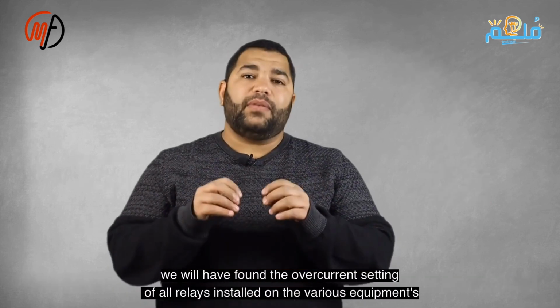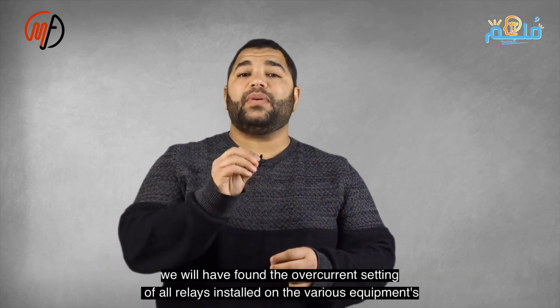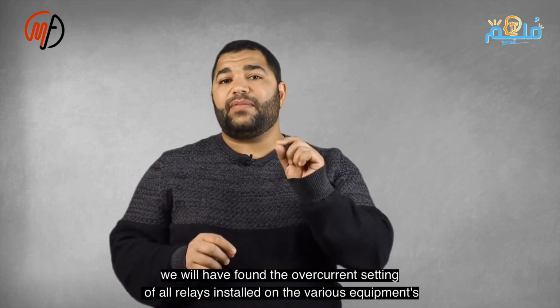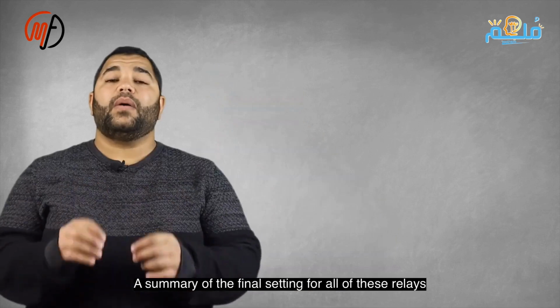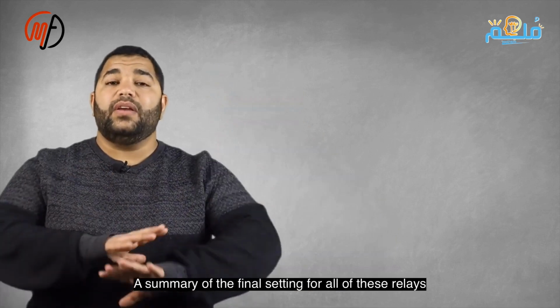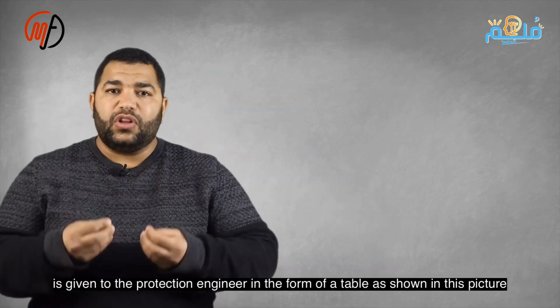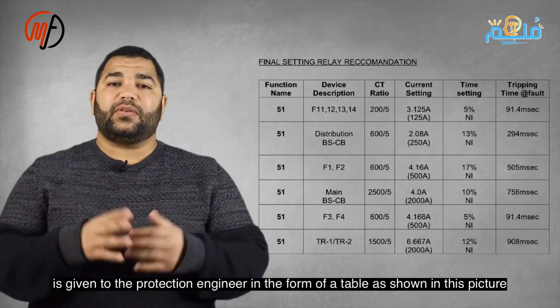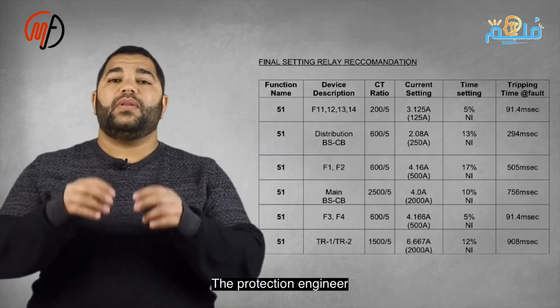And in this way, we found values for all relays. The engineer receives a summary table, inputs specific values, and checks safety. Curves are in ETAP software. For time coordination using the definite time curve on overcurrent relays, it's easier. Coordination follows the table with pickup current values and trip times.